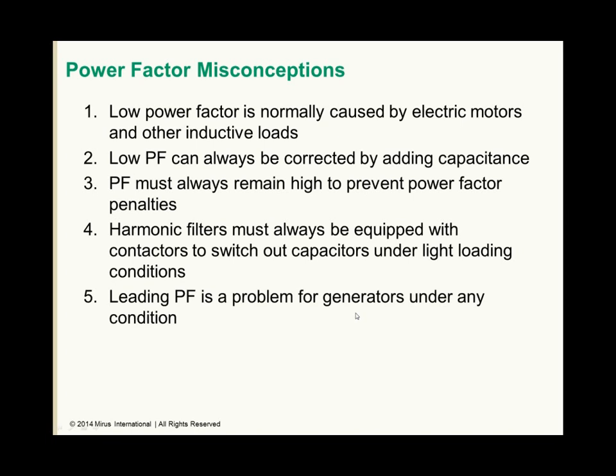Fifth is that leading power factor is a problem for generators under any condition. It is true that a leading power factor that results in high levels of capacitive reactive power is a problem for synchronous generators, but in certain conditions, power factor can be low and leading without there being too much capacitive reactive power for the generator.